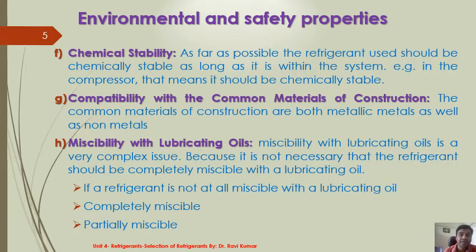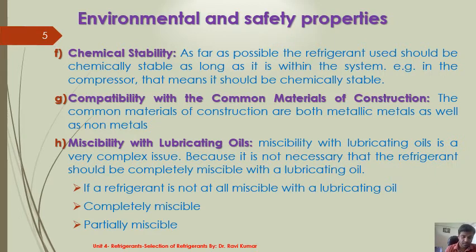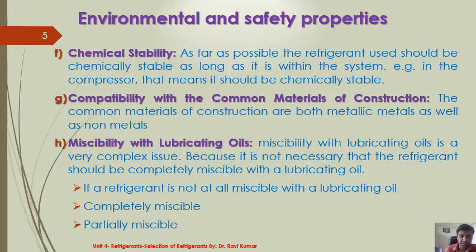The next point is miscibility with lubricating oils. This is a very complex issue because it is not necessary that the refrigerant should be completely miscible with lubricating oil. If a refrigerant is not at all miscible with lubricating oil — for example ammonia, which is not miscible with lubricating oil — then we install an oil separator at the exit of the compressor so that oil can be collected from the refrigerant vapors and sent back to the compressor, so that the oil does not circulate through the system.